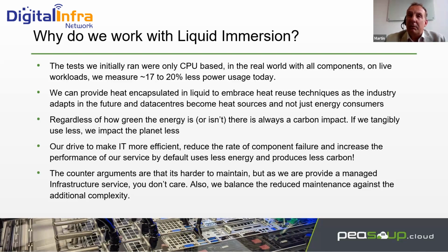We could raise the base level quite happily and still not come anywhere near the stresses that would be under air. So we'd happily put that out to cooling rather than chilling. The other side is we're also ready for when the data center realizes how to become a heat source - when it looks at being able to take liquid, put it through a heat exchanger, pass that off to heat networks, and reuse the heat. So it's not just an energy consumer; it's actually providing back into the local environment. Then we're ready for it because we're encapsulating the heat immediately into liquid.